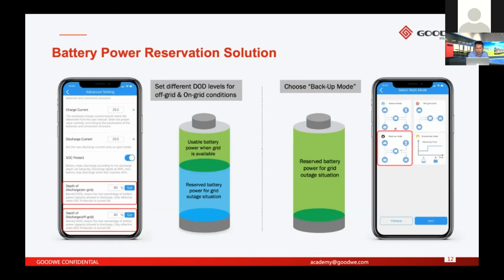If you do not have off-grid DOD settings, it means if the grid is okay and the load power is high, the battery may discharge all its power to supply the loads. Under this condition, if the grid fails, the battery does not have enough power to supply the loads. So different DOD solutions are for scenarios where the public grid is not stable.